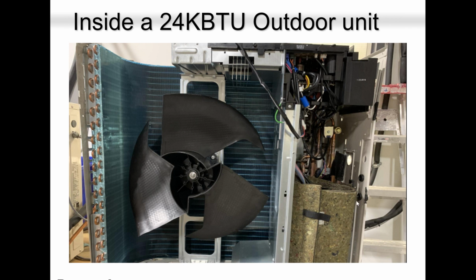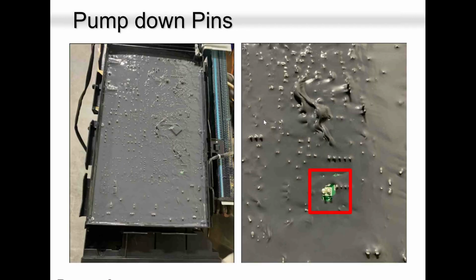When you open up the front cover, you are exposed to everything. You have access to the fan, the board, the compressor, the four-way valve, everything. And the electronic expansion valve is at the back, so you might have to open up the side cover. Then when you open up the top cover of the unit, you will see this PCB here. This is the top view, and this is the back of the condenser. This is the back coil of the condenser. The fan motor is somewhere here down, and this is the PCB.